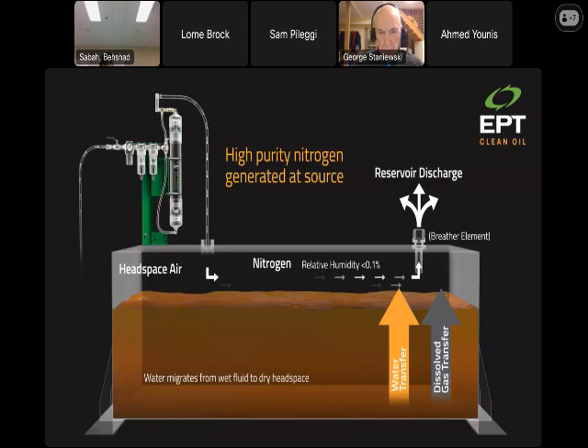If you put a vacuum dehydrator on an oil system where the ingress pathway is atmosphere, you're just dehydrating the fluid so that it can remove more water from atmosphere. You're creating a very energy intensive cycle. Vacuum dehydrators have their place. They're actually essential. They're great tools in the right application, in the right place, but not when the ingression source is atmosphere.